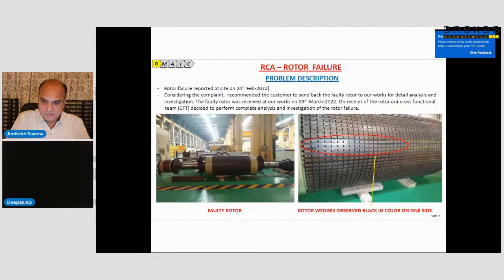Yes, this is the problem description. You can see the rotor failure was reported on 24th Feb 2022. Considering the complaint, we recommended the customer send back the faulty rotor to our works for detailed analysis and investigation. We received the rotor on 9th March. On receipt of the rotor, our cross-functional team decided to perform a complete analysis and investigation of the rotor failure.